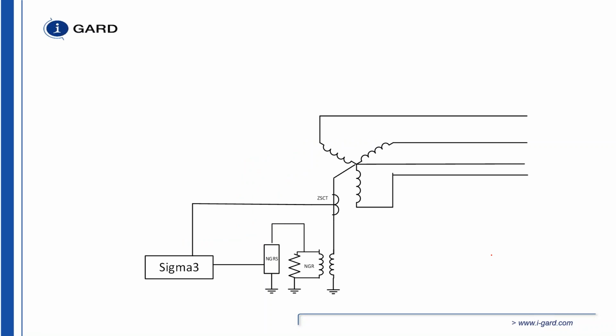Now the problem is some transformers or generators are close coupled with a transformer, and you load the secondary of the transformer with the resistor, and it's difficult to monitor the integrity of the resistor. The resistor is easy to monitor, but we can't monitor the line going to the neutral. So do we have to put two sensing resistors and sensing relays in here, one to monitor the line going to the neutral and one to monitor the resistor?